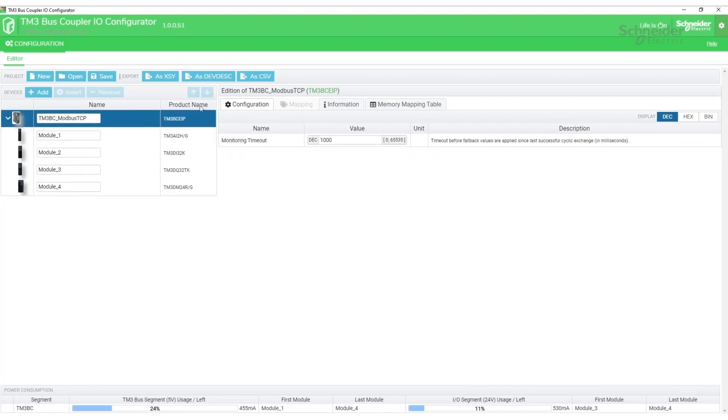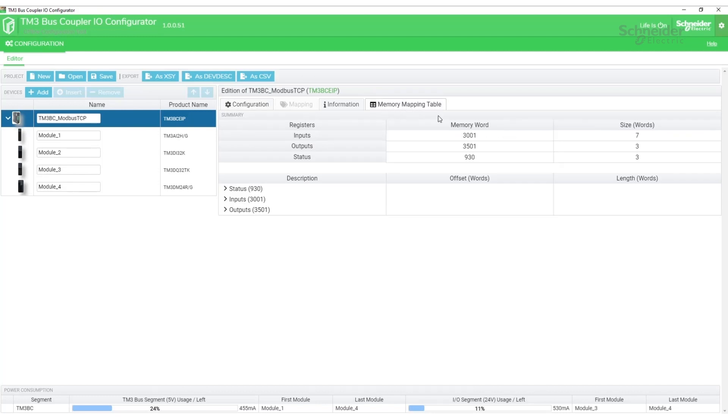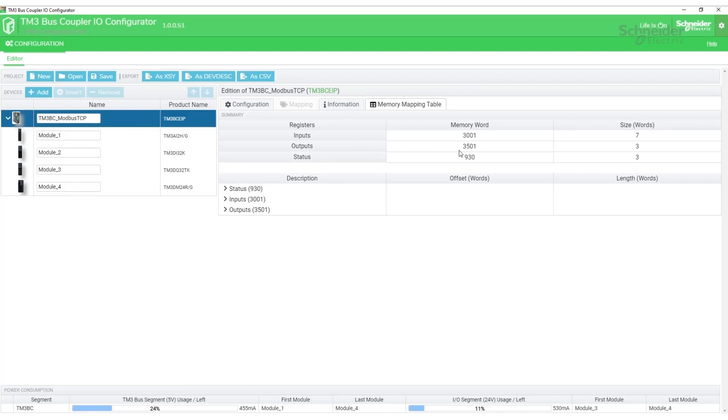Now that I have the module set up, I'm going to go to the bus coupler again and go to the memory mapping table tab. This tab is what's actually going to tell us where the registers are located that have the data from these modules. All my input data is going to be located at 4x3001 with a size of seven words. All my output data will be accessible at 4x3501 with a size of three words. We're going to need this information when we set up the communications in the DTM browser on the M580.